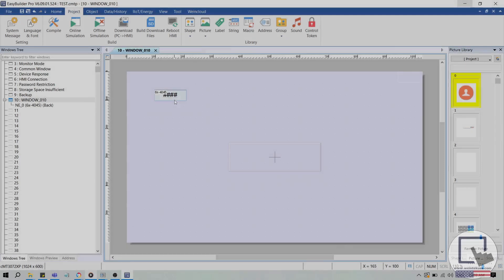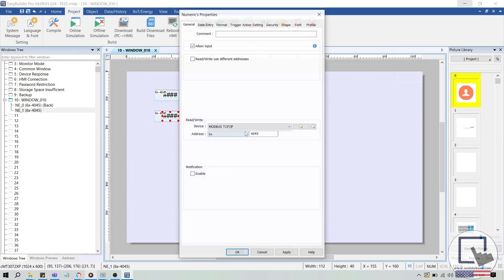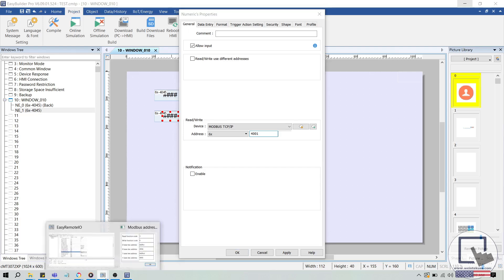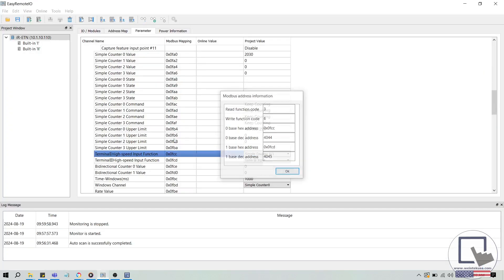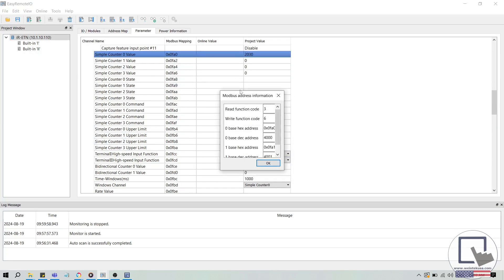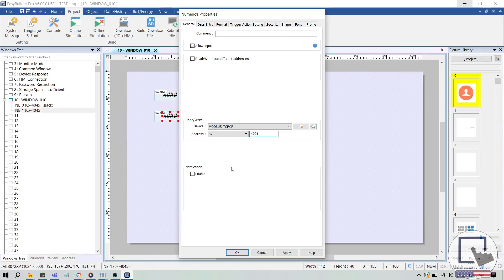I'll add the simple counter 0 value using the address 6x4001. In this case, I'll change the data format of this object to 32-bit unsigned in order to accommodate larger values and to match the data type of this parameter. Then, I'll run the simulation again so that we can view the counter value in real-time.